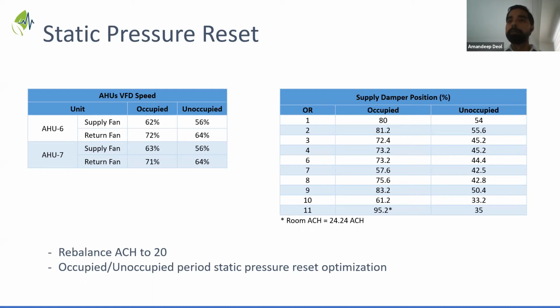That means most of the pressure across that fan is being wasted across these dampers. During the occupied mode, all of them are below 80% except one room, which is at 95%. Looking at the air testing reports, that room is currently at 24 air changes, so it should actually be at 20 air changes.